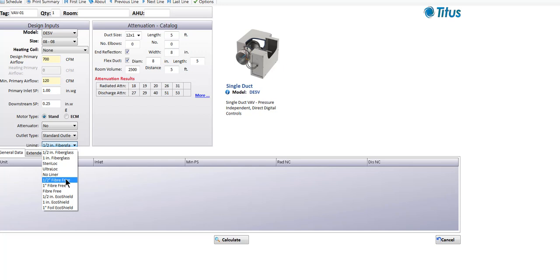Because fiber free lining can't absorb any moisture, anyone using this material needs to mechanically fasten it inside boxes. We apply it with a hot melt glue to hold it initially and allow it to get tacky, then come back with weld pins to secure the material mechanically. We want to glue it so air can't get back behind it, but we rely on the mechanical fasteners to hold it in place permanently.